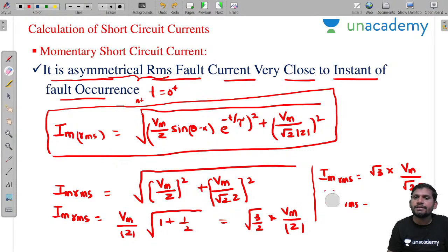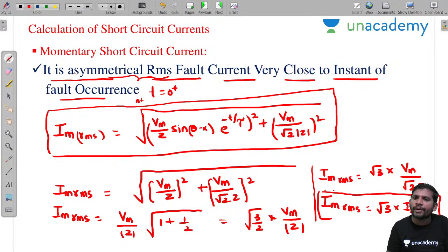Yes sir, RMS value of momentary short circuit current. Im RMS equal to root 3 times Vm by root 2Z, the symmetrical current. This momentary current is a very important consideration in the selection of circuit breakers. In the rating selection, Im RMS equals root 3 into Is symmetrical current, but generally we do not take root 3 times mainly in circuit breaker selection.